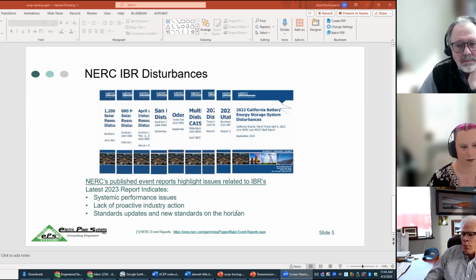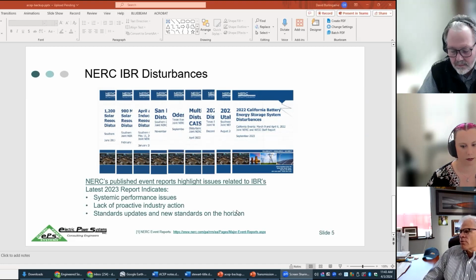One of the big problems with IBRs, and it's not just IBRs, it's any new generation like the new gas generation, is the exact same problem. When you do a small signal test to try and get a model to put into your system planning, that small signal test doesn't test all the functions of the IBR, the same way it doesn't test all the functions of a gas-fired generator anymore.